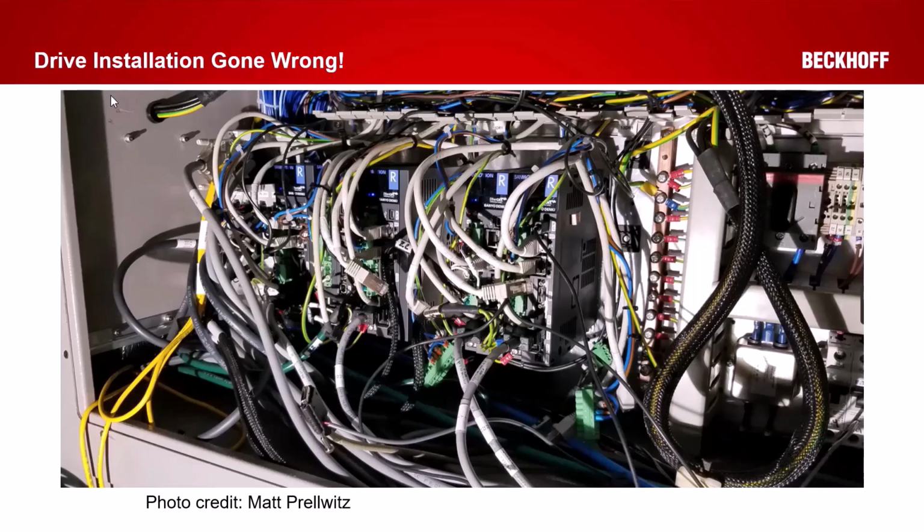I was helping out with the system, and we were struggling getting the drives to communicate into our TwinCAT software. The drives were EtherCAT compatible, but we couldn't communicate to them. So I'm like, oh, we got to look. Maybe the drives, maybe a fuse is blown, a circuit breaker's tripped. Popped open the cabinet, wires fell out of the cabinet, and I had to take a picture of this.